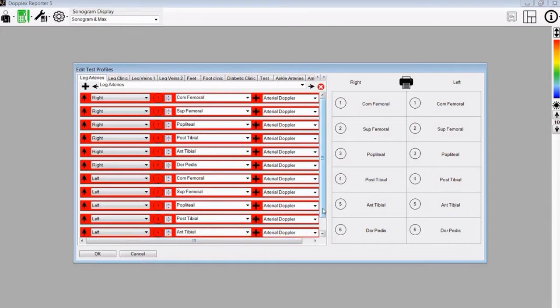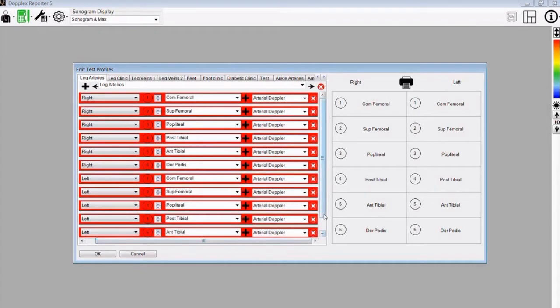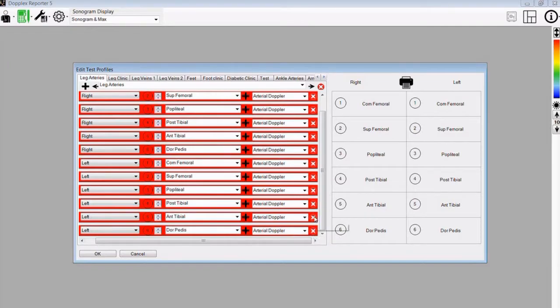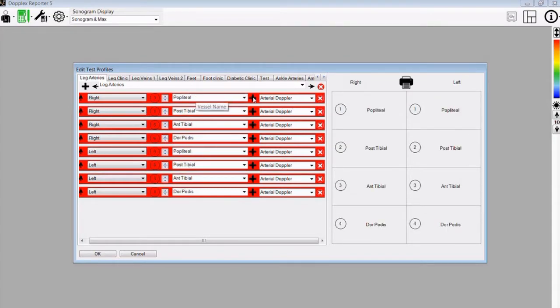First of all, we will show you how to edit an existing profile. If there are too many vessels that you want on the leg arteries test, you can easily delete some by selecting the red cross on the right hand side. For instance, we do not want to do the femoral artery or the superficial femoral artery, so we can delete those from the profile. The order in which these are shown is the order in which you do the test, and the right hand side shows the print order. Once you are happy with this profile, press OK and the changes will be saved.